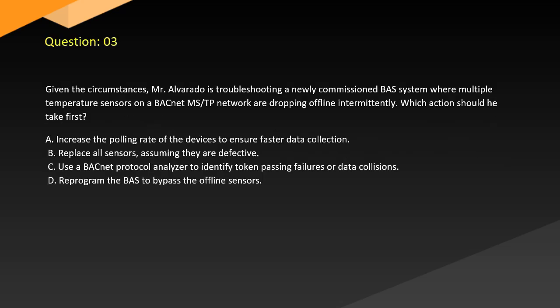Question 3. Given the circumstances, Mr. Alvarado is troubleshooting a newly commissioned BAS system where multiple temperature sensors on a BACnet MS/TP network are dropping offline intermittently. Which action should he take first? A. Increase the polling rate of the devices to ensure faster data collection. B. Replace all sensors, assuming they are defective. C. Use a BACnet protocol analyzer to identify token passing failures or data collisions. D. Reprogram the BAS to bypass the offline sensors.